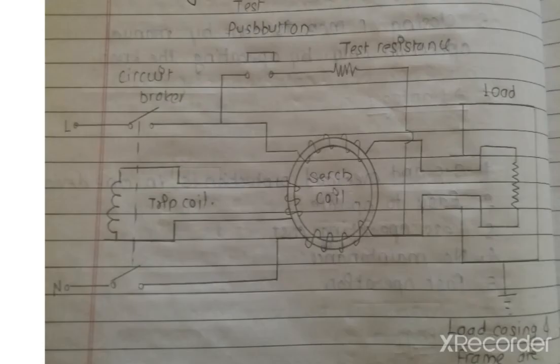Now we are discussing the ELCB. ELCB means earth leakage circuit breaker. According to the construction, there are mainly two lines. This is the live phase and this is the neutral phase. And there are two identical coils, one for the live conductor and one for the neutral conductor. The search coil, which is the secondary coil, is used for the trip coil. This main contact, which is opening and closing, is operated by using this trip coil, and this search coil sends the signal to the circuit breaker.